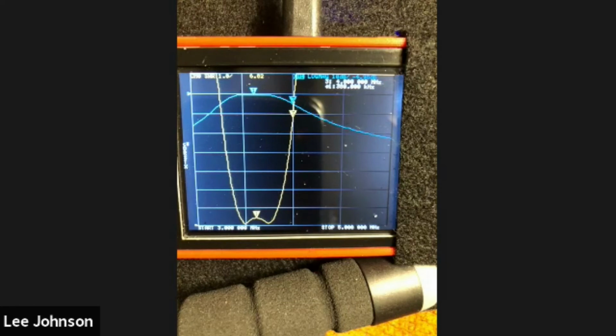Let's say I calibrate for 3 megahertz to 30 megahertz, and then I recall that calibration, but then I set the sweep for just the 40 meter band or the 20 meter band. Would that be valid? Well, let's think about it for just a minute. Or do I need to calibrate for the smaller segment of the band or whatever I intend to measure, really? Well, everything you've seen tonight was done with no new calibrations for a smaller scale. The calibration I've got running tonight is the 50 kilohertz to 30 megahertz calibration. Okay, so when I looked at the individual smaller bands, I didn't recalibrate.